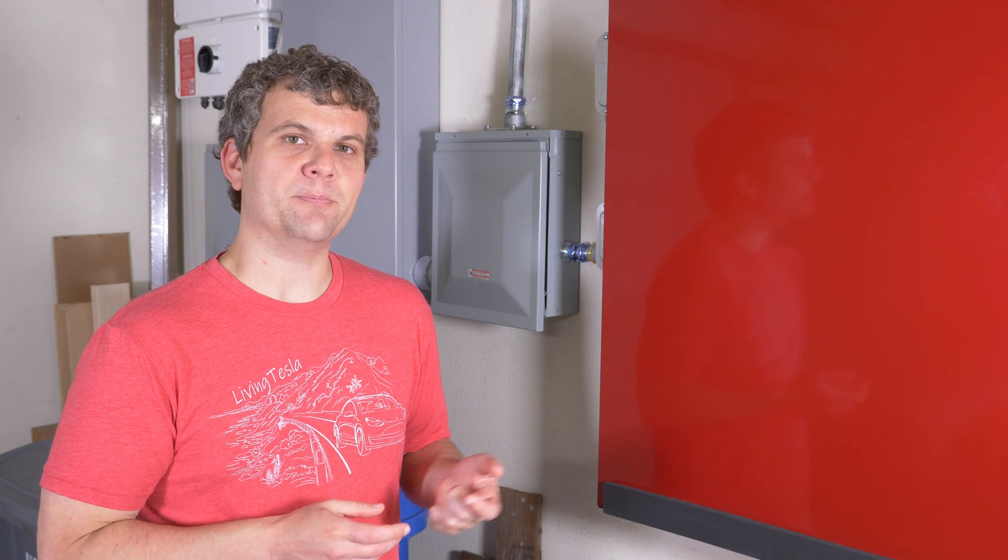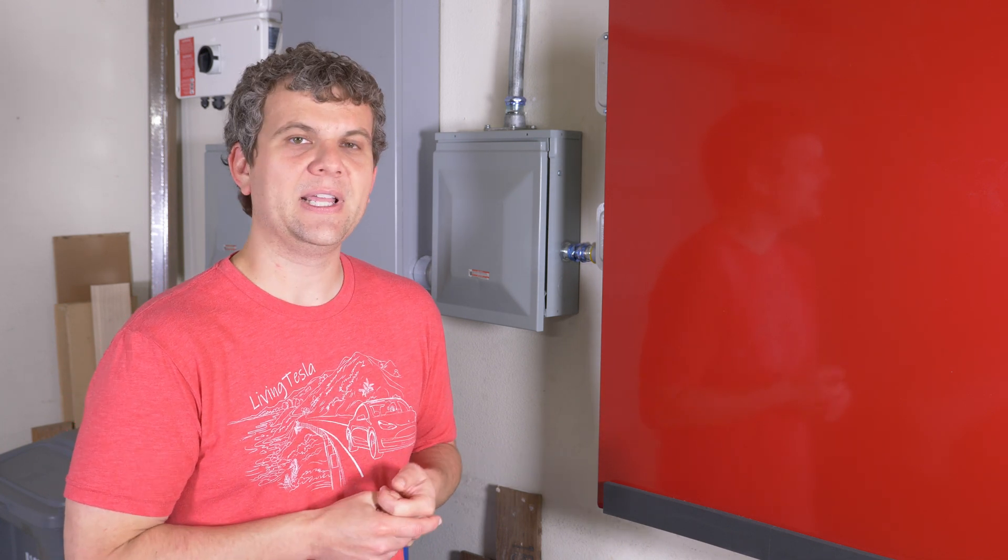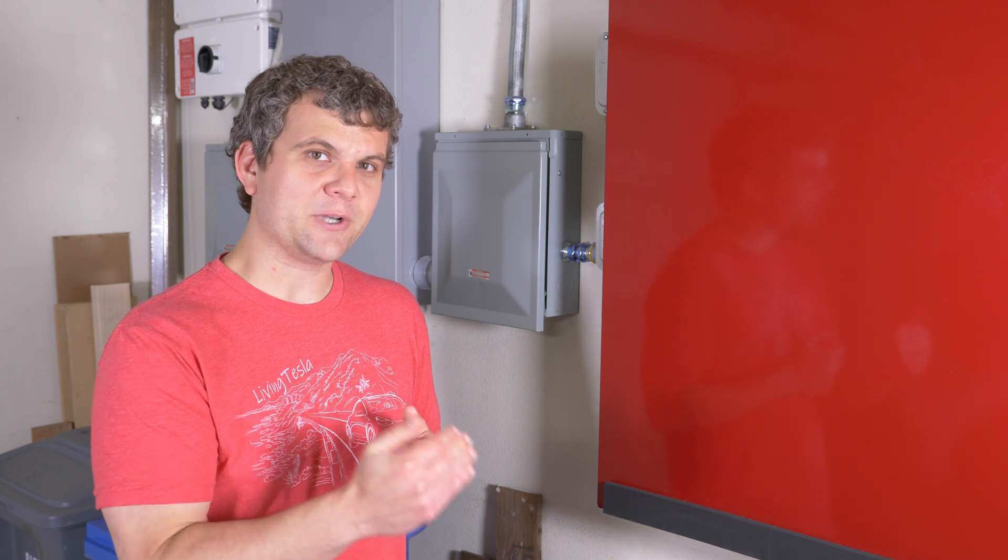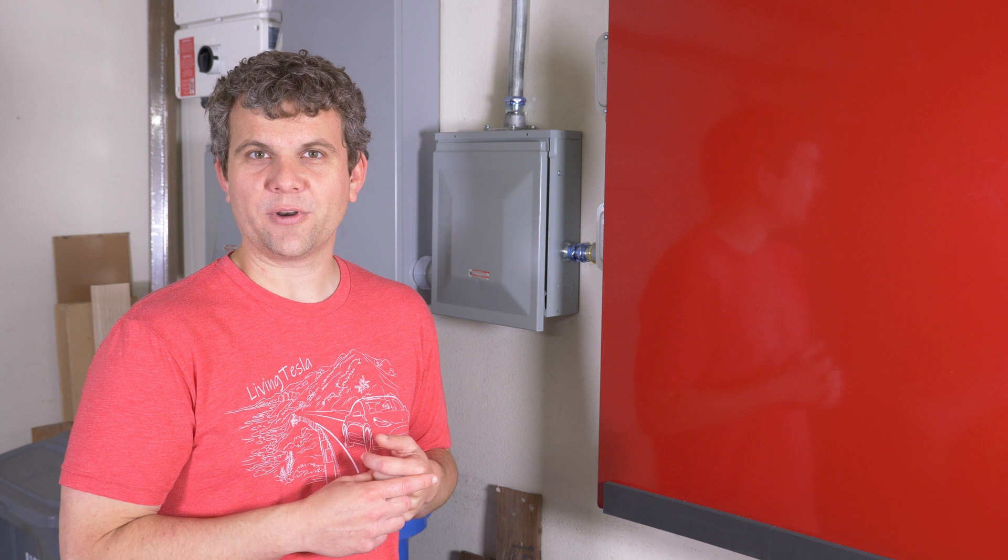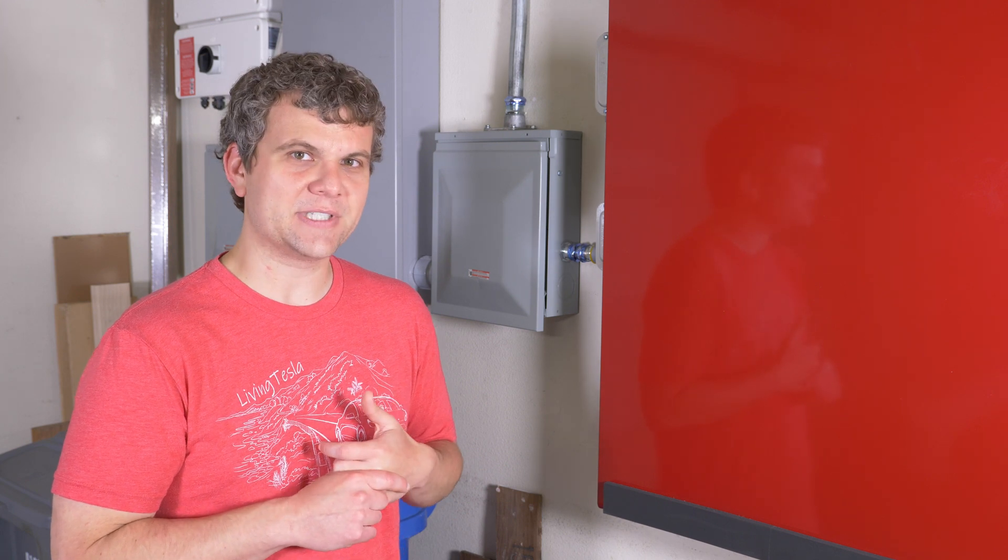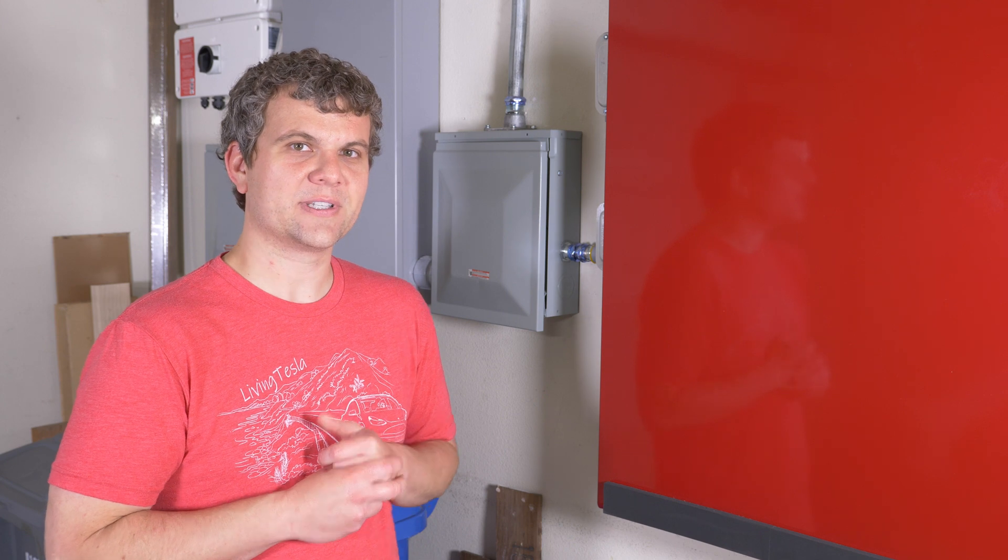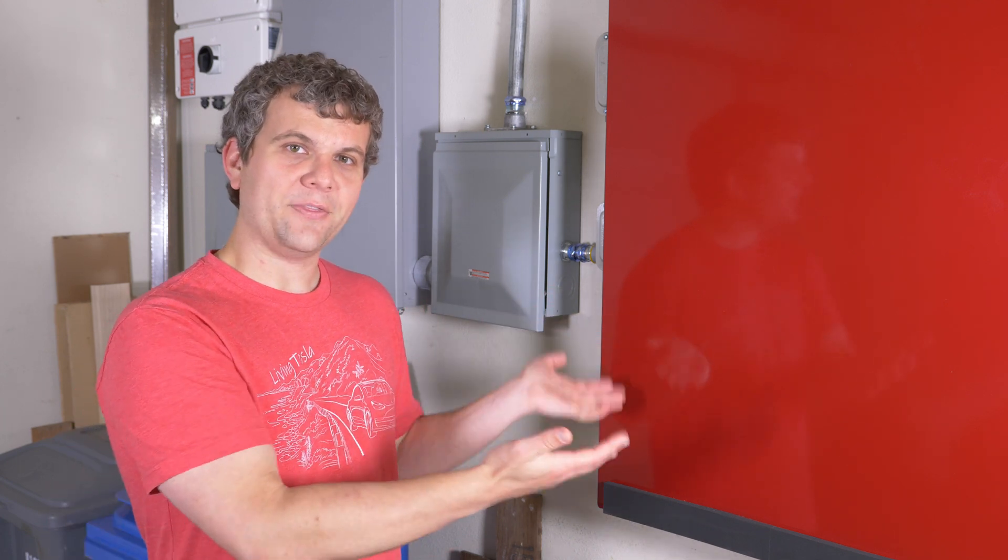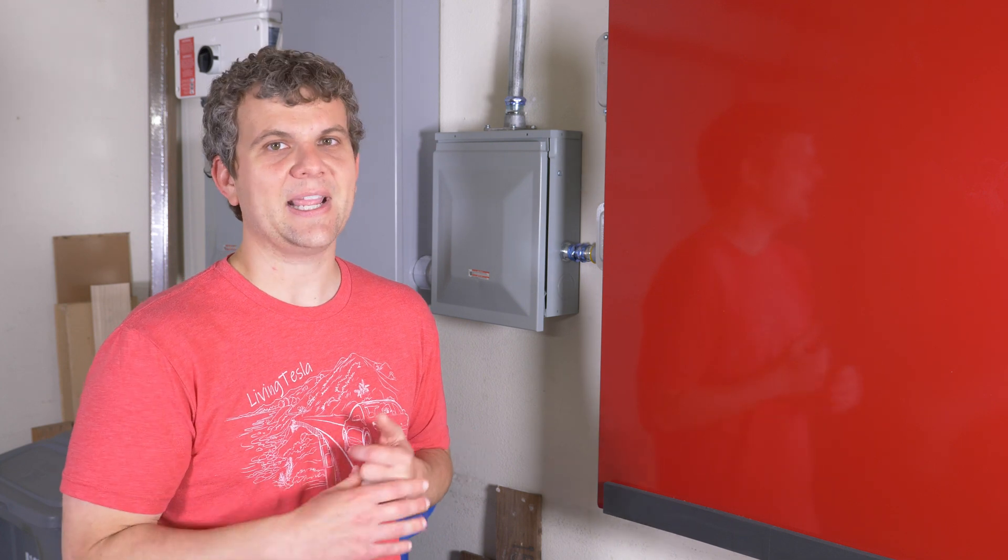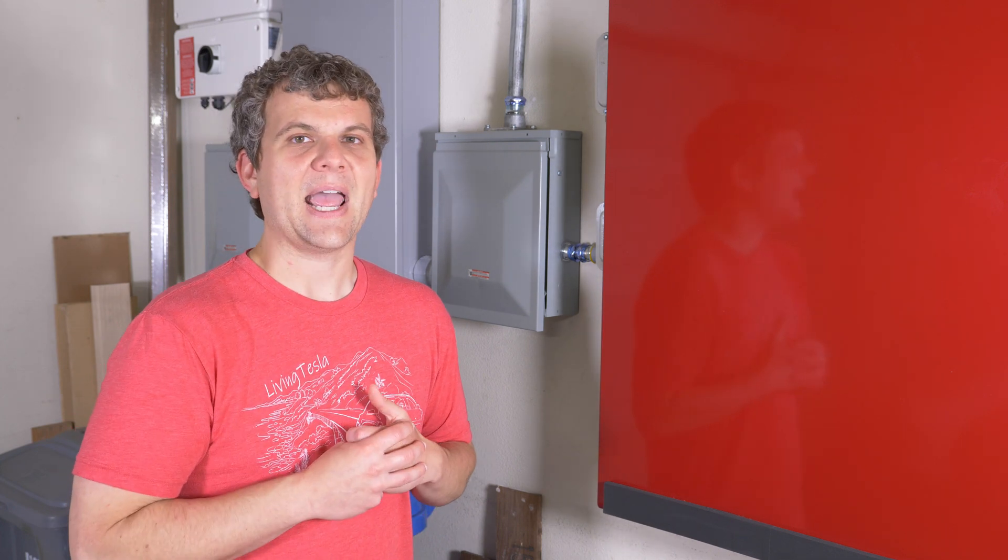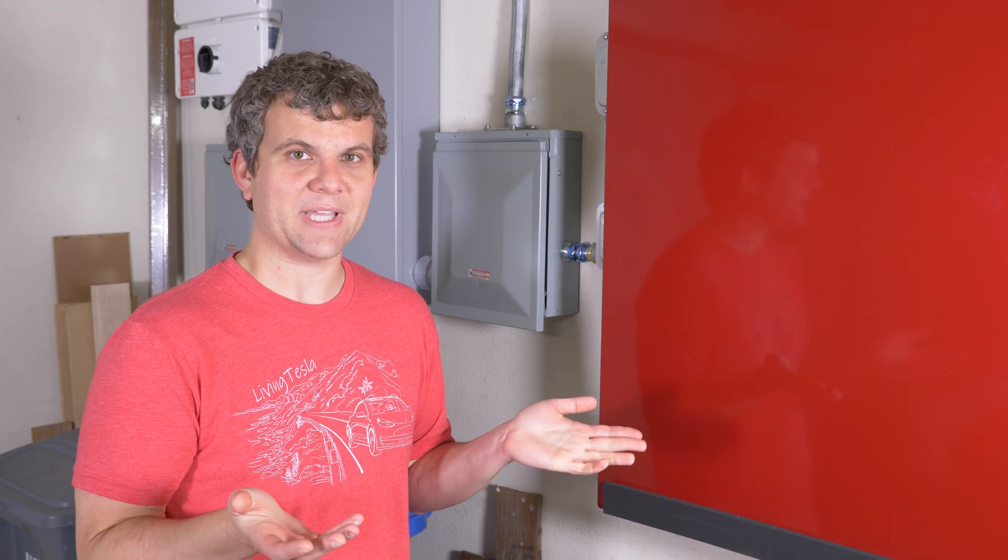They asked me which model of UPS I have and they asked me to look in the manual and see what its high frequency setting was. And for mine, it's a CyberPower 1350 PFC LCD and its high set point is 62 Hz. So supposedly they've changed my system now to go to 62 Hz instead of 65 Hz, and they asked me to test and see if the UPSs are now happy with that.